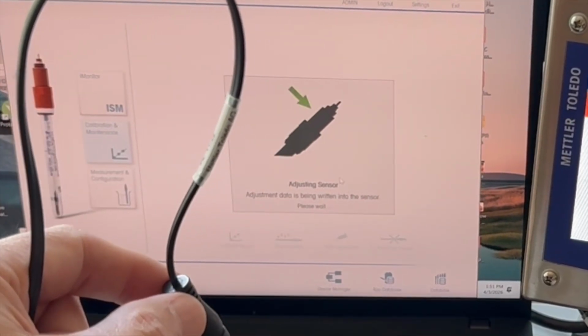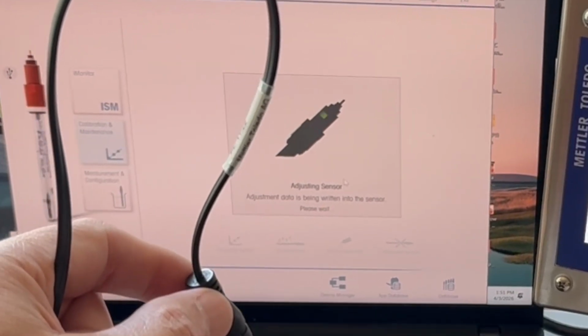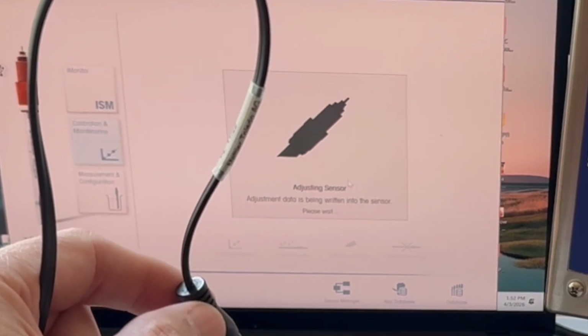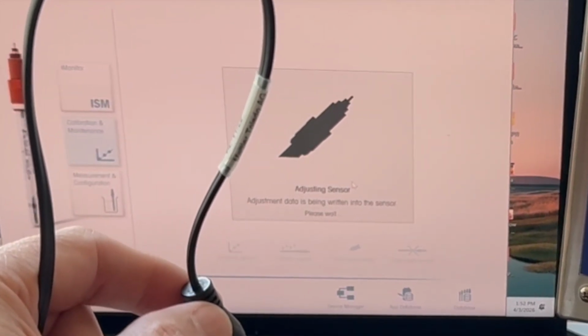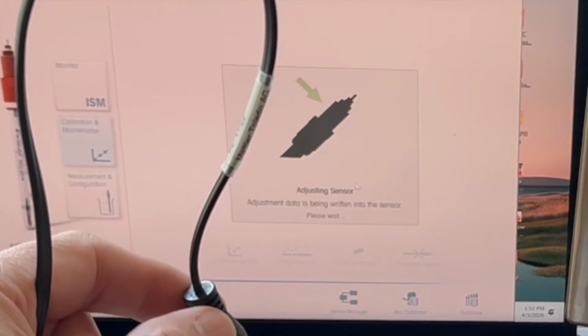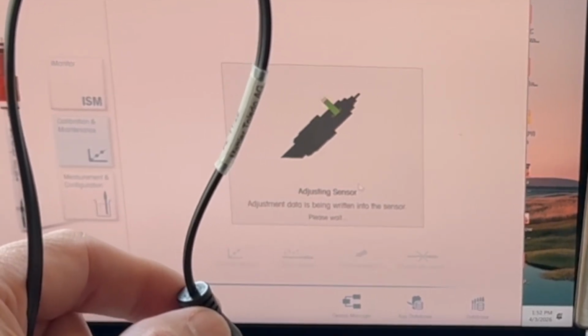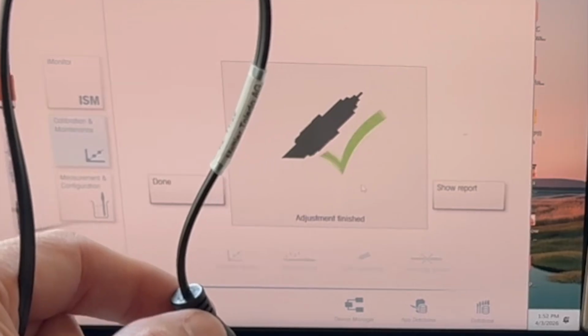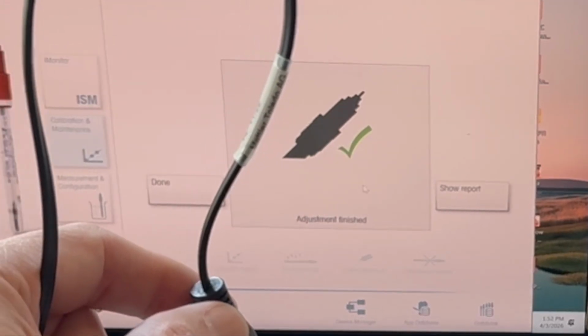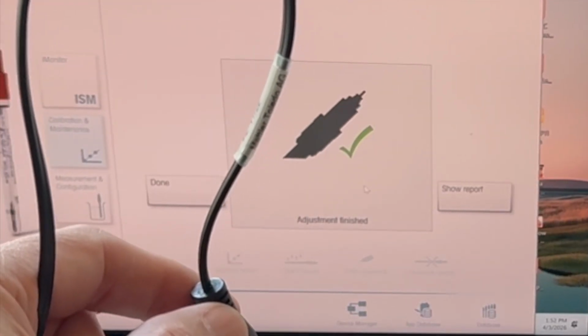I could put that information in there, but I'll just say skip. And we wait for the sensor to have the new slope and offset data loaded onto the head of the sensor. So now it's married to the sensor, not the transmitter. In the days of analog sensors, which a lot of people still have, you can't do this. The calibration data resides in the transmitter.